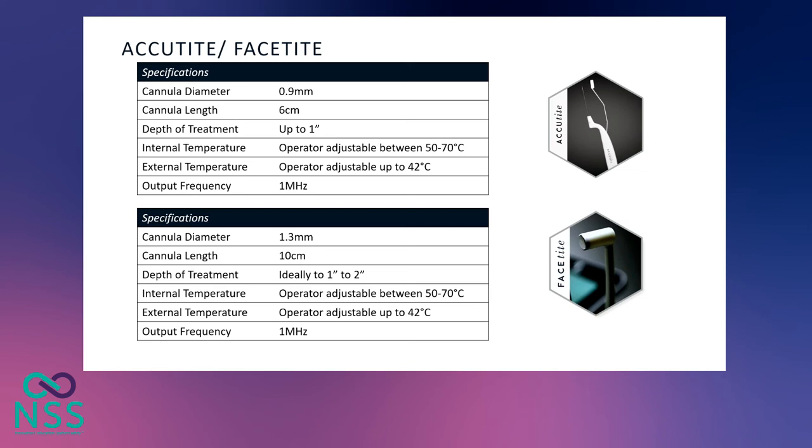For both the Accutite and FaceTite, the physician can preset the cutoff temperature for the internal and external electrode. For the internal electrode, the temperature is adjustable between 50 to 70 degrees, and the external temperature up to 42 degrees. Above 42 degrees we can cause skin damage, and we need the internal temperature to be above 55 degrees for subcutaneous contraction.